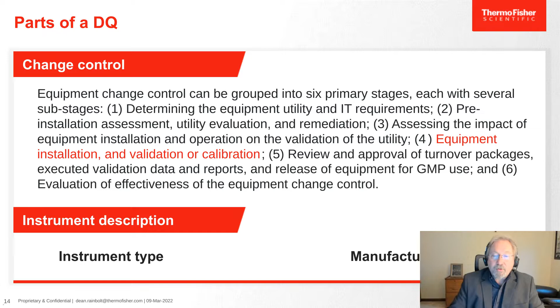And the user requirements. This is one of the most important parts of a DQ. This is what's going to sell it to your quality unit. So it's kind of, what do I have to have, and what would I like to have? So intended use, what is your intended use? Well, today our intended use is for storing critical samples because our samples are important. And we want the desired temperature of minus 80 degrees C.